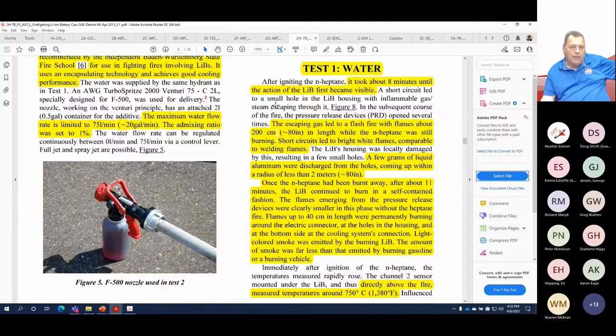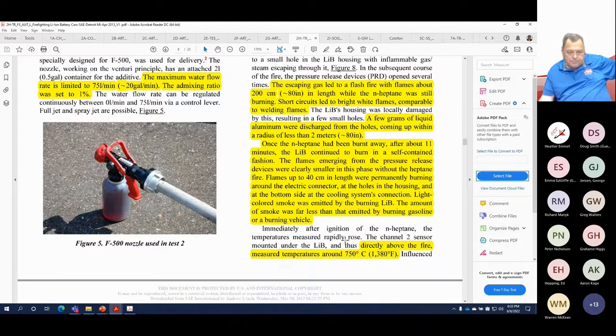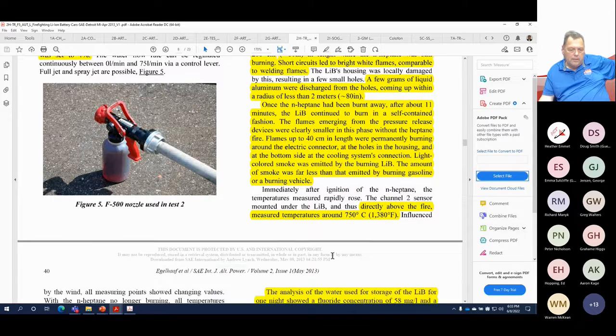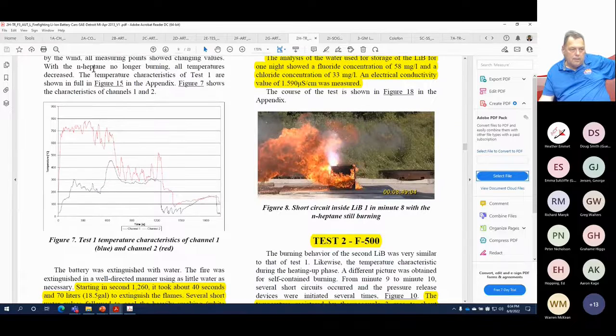Test 1: it took about 8 minutes until the action of the lithium-ion battery became visible. Escaping gas led to flash fires with flames about 200 centimeters in length while the heptane was still burning. Short circuits led to bright white flames. A few grams of liquid aluminum were discharged through holes once the heptane had burned away. After 11 minutes, it continued to burn in a self-contained fashion. The flames emerging from the pressure release devices were clearly smaller in this phase without the heptane. Flames were up to 40 centimeters high. So it just talks about it directly above the fire. The temperature was 750 degrees C. So here they're showing 750 degrees C.